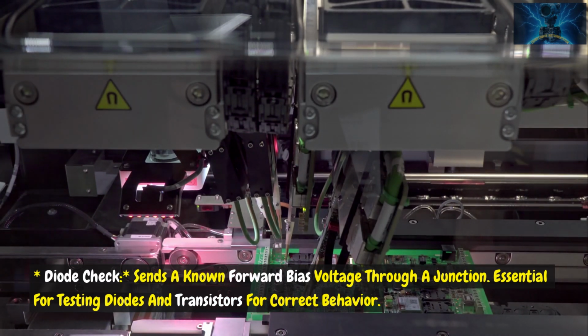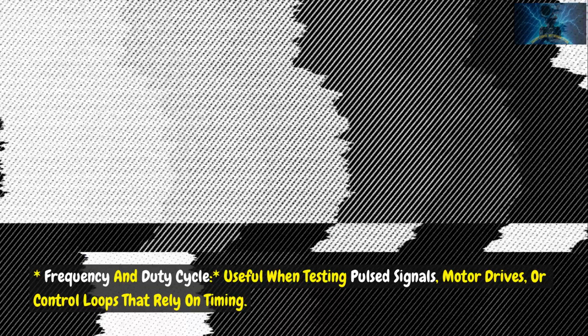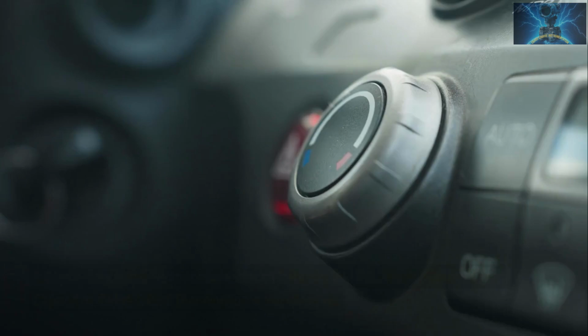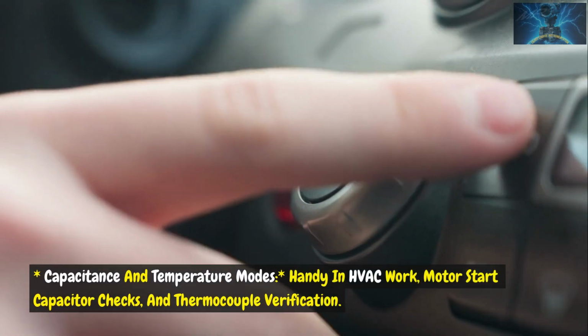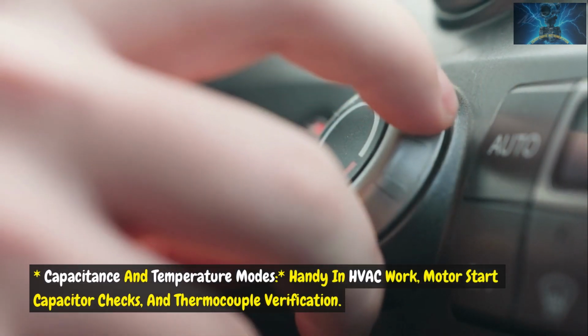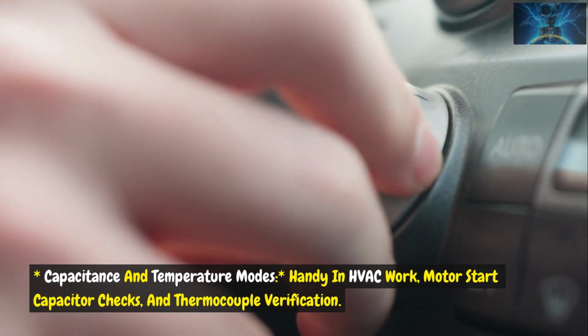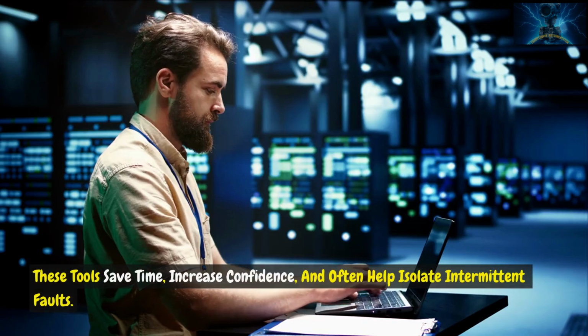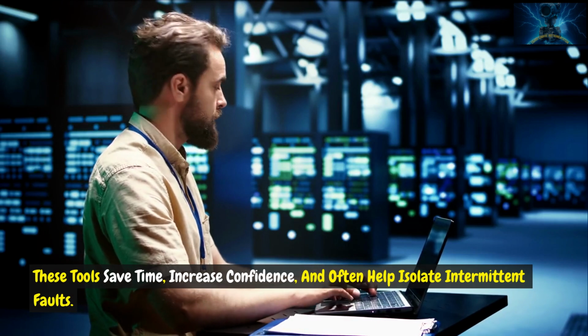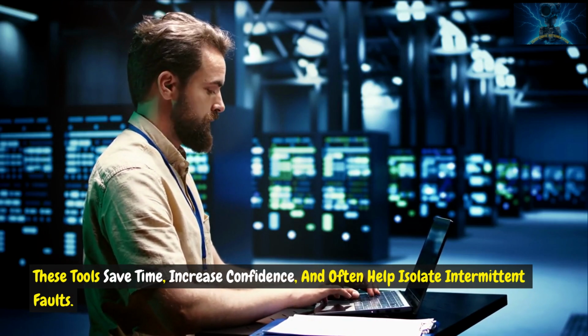transistors for correct behavior. Frequency and Duty Cycle are useful when testing pulsed signals, motor drives, or control loops that rely on timing. Capacitance and Temperature Modes are handy in HVAC work, motor start capacitor checks, and thermocouple verification. These tools save time, increase confidence, and often help isolate intermittent faults.